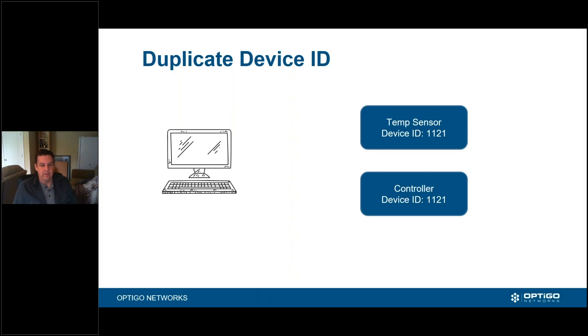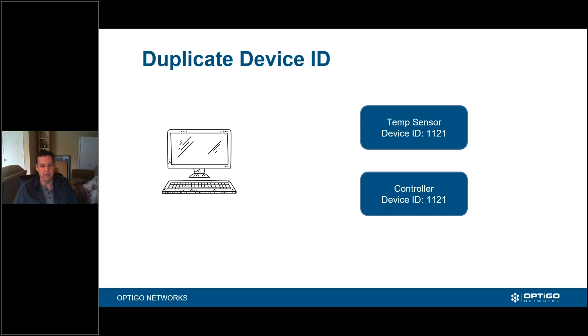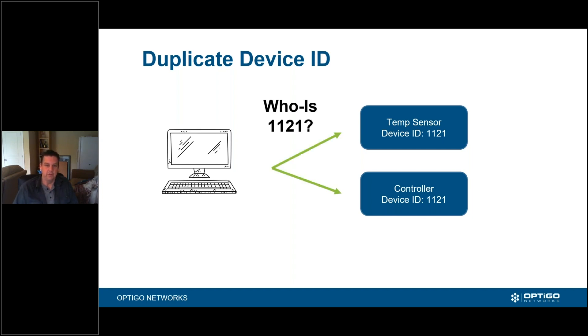Duplicate device IDs are a nasty thing that happens when you take your BACnet device ID and put it on more than one controller on the network. The byproduct is very difficult to detect. Usually, for example, you have a temperature sensor with BACnet ID set to device 1121, and a VAV controller also has the same device ID — because these are software addressed, somebody didn't update a list, or you went on a coffee break and started back with your last number. It's very easy to make this mistake.